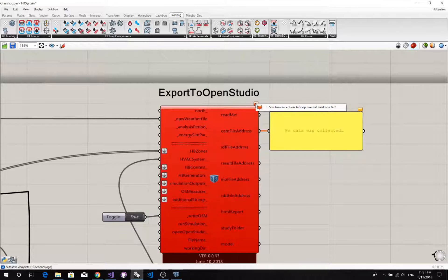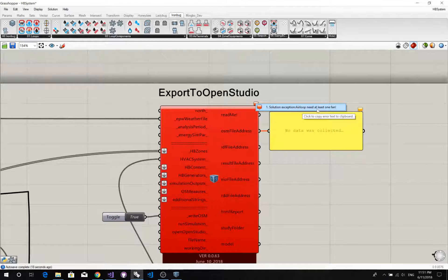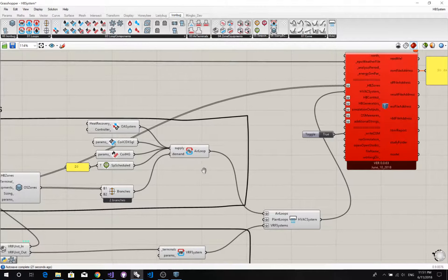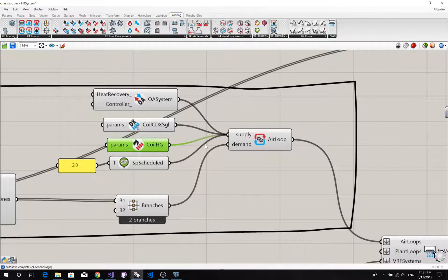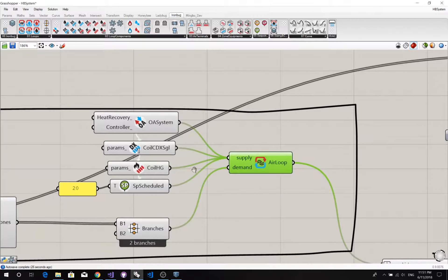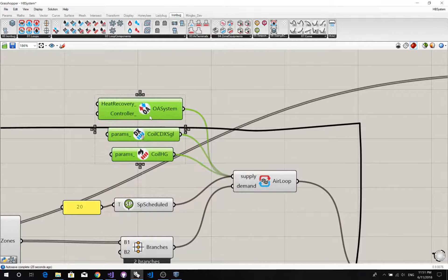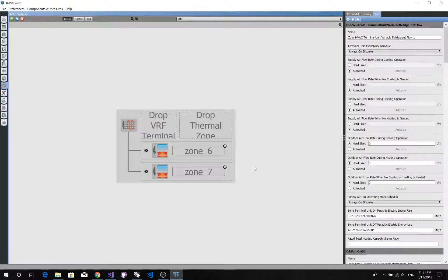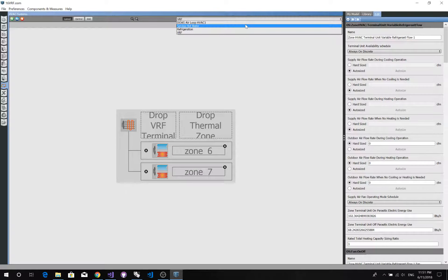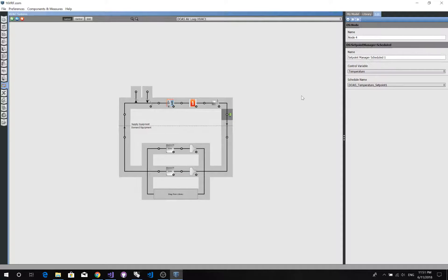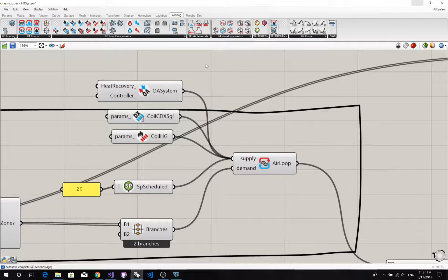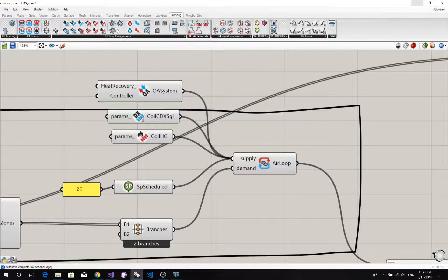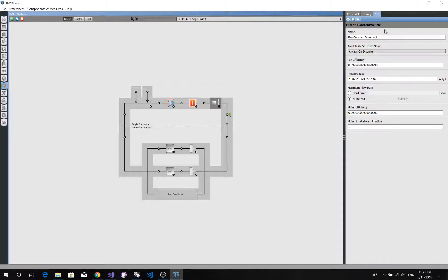It tells us air loop needs at least one fan. So where's our air loop? Oh, we missed our fan. In between, I guess in between the heating coil and the setpoint manager. So in this loop, we have a constant volume fan.